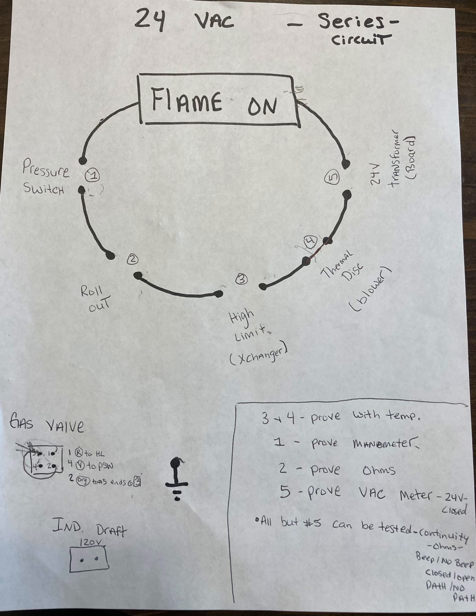So in order to do this, the switch needs to close. Once the temperature has cooled down, that switch should close back up. We can prove this with the power off. The switch is isolated, continuity, ohms signal on our meter. We beep over to it, and there we go. Do we have a beep or do we not?